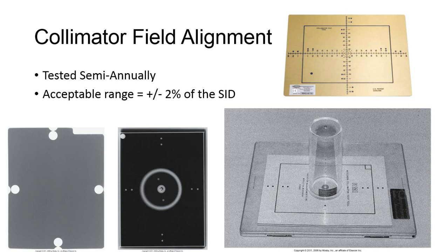The idea is that since a penny measures slightly more than 1.9 cm, if you can visualize the entire penny on either side of the collimated field on your radiographic image, you'll be outside acceptance limits using a 100 cm SID. The collimator field alignment test should be performed semi-annually.